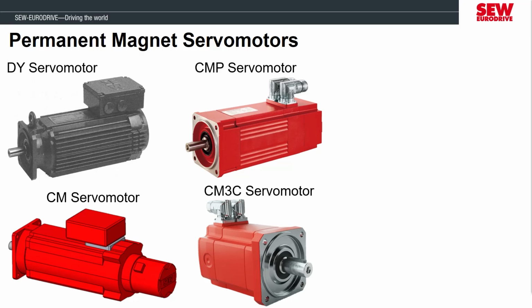The easiest way to identify a servomotor from an induction motor is its shape, and it doesn't have a self-cooling fan. The CM motors have a smooth housing instead of the cooling fins that you'll see on an induction motor. However, it is possible to have a cooling fan on a servo, but it has to be externally powered since servos don't have a shaft extension out of the back to attach a fan.